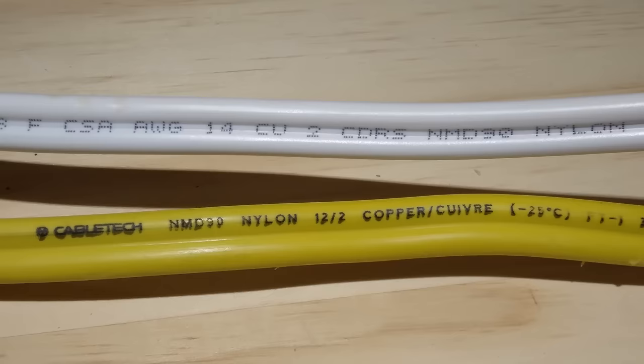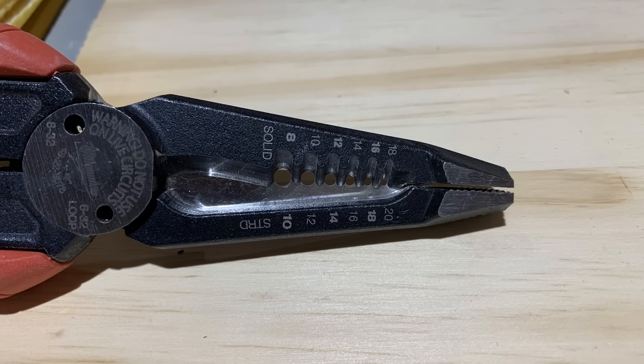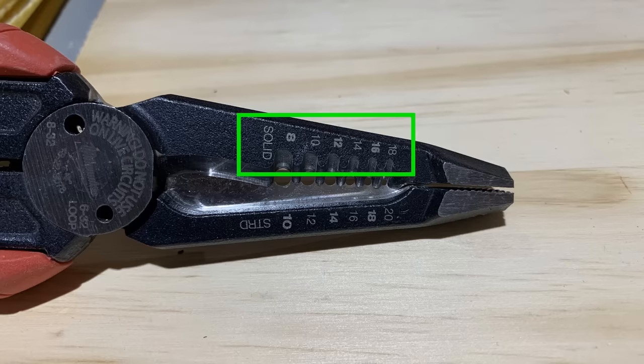In North America, typically white Romex is 14 gauge wire and yellow Romex is 12 gauge wire, but check the labeling on the outside of the sheath to confirm. Make sure you line up the wire with the correct cutter slot. If your cutters have markings for solid and stranded wire, like my Milwaukee six-in-one electrician's pliers do, make sure you use the solid wire markings.